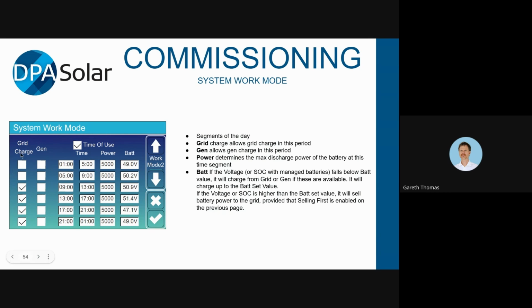The column on the left-hand side is grid charge. And so if that's enabled, during that selected period, it will allow charge from the electricity grid in that period. The same with the gen column. If you have that ticked for whatever time period you've ticked it, it will allow generator charge in that period. So if you're in an off-grid scenario and you didn't want the generator to start at night, you could perhaps have a time period set for the evening where you have the generator unticked. The power determines the max discharge of the battery during this time segment for selling to the grid.